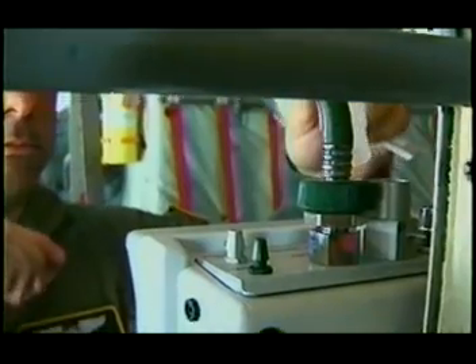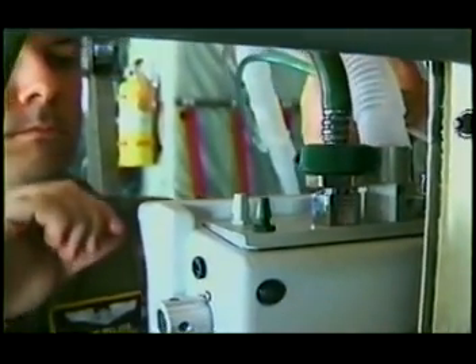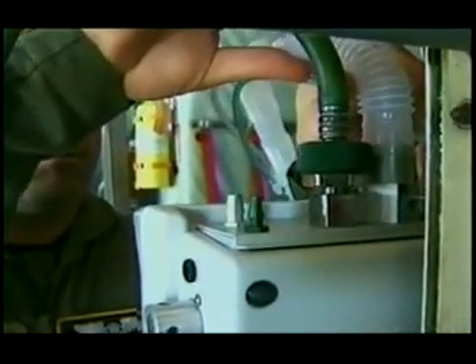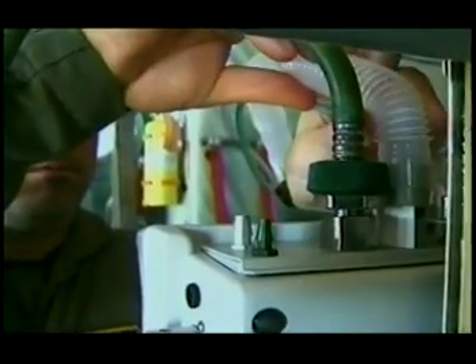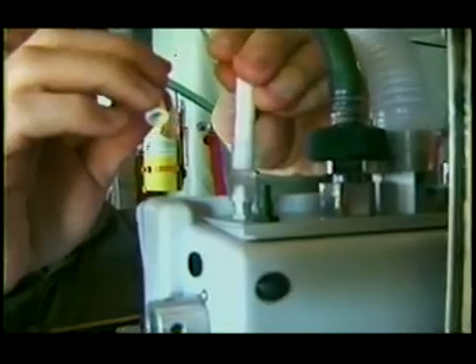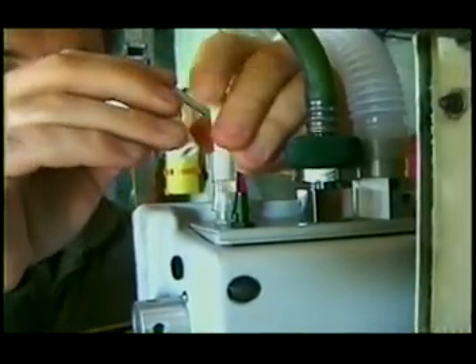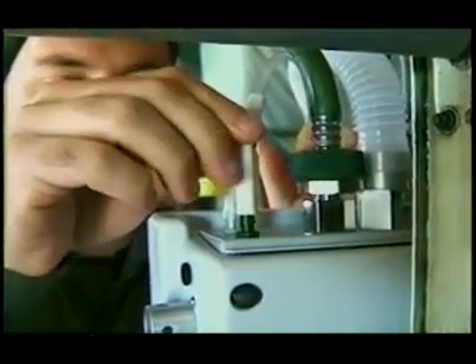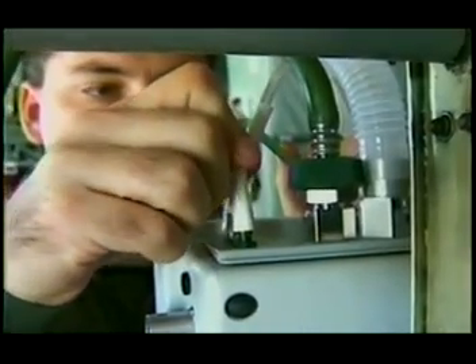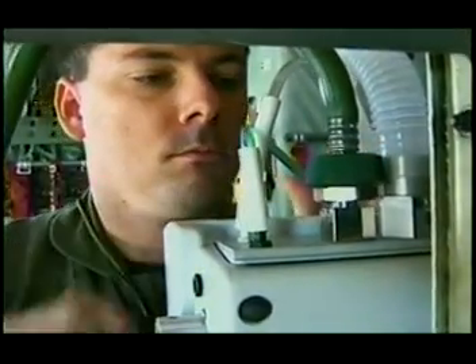Carefully connect each of the 3 ventilator circuit hoses. The 22 millimeter hose attaches to the large fitting labeled gas out to patient. And the clear hose attaches to the hose barb fitting labeled exhalation valve. The green hose attaches to the hose barb fitting labeled transducer.